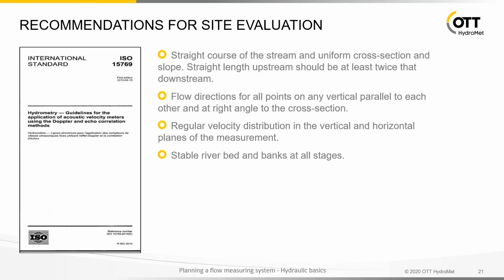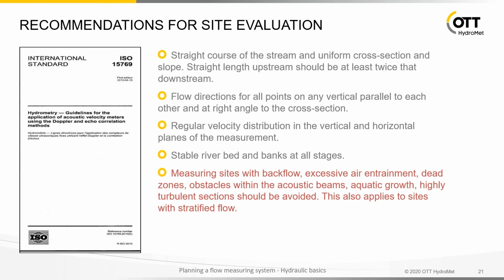If you have erosion on site or deposition and the bottom elevation will change, then the computation of the discharge in the end is affected by these changing conditions, and the index rating will be unstable. And what you should avoid is sites with backflow, sites with excessive air entrainment for acoustics here, dead zones where water is not moving. You need to avoid obstacles within the acoustic beams.